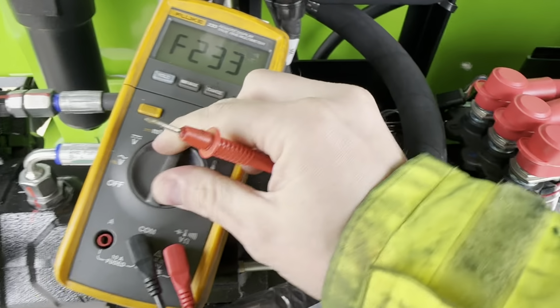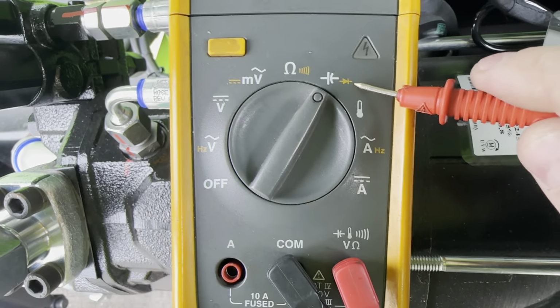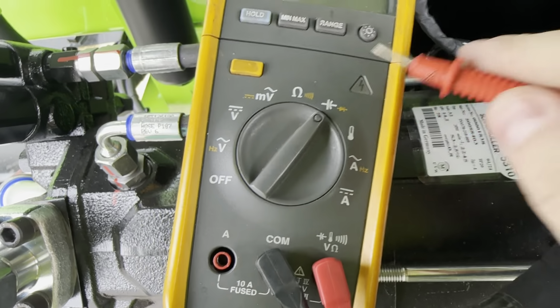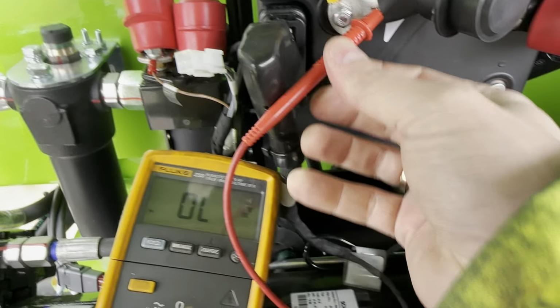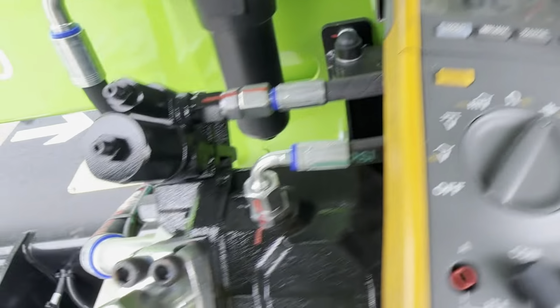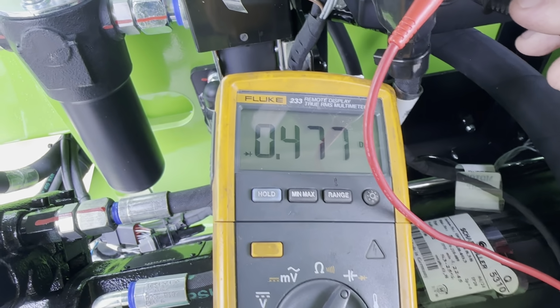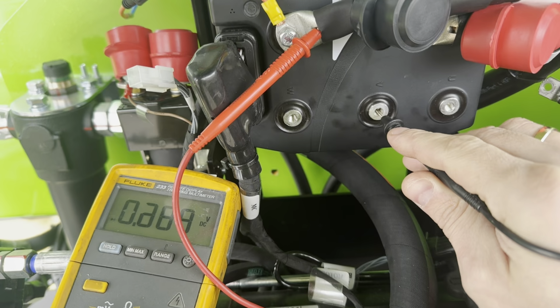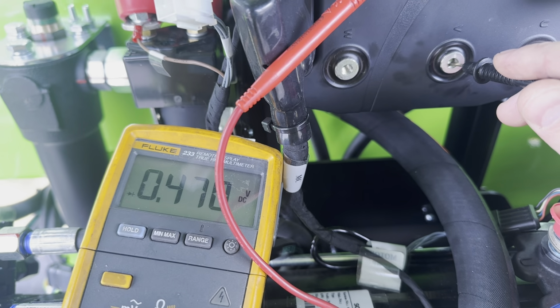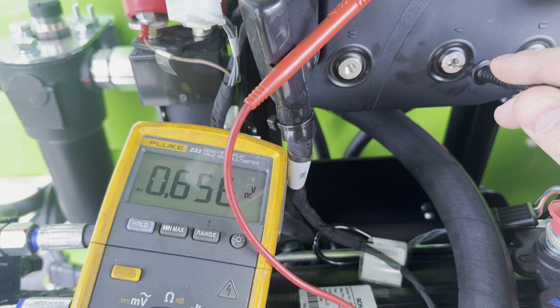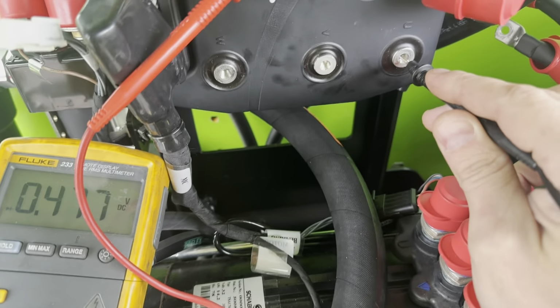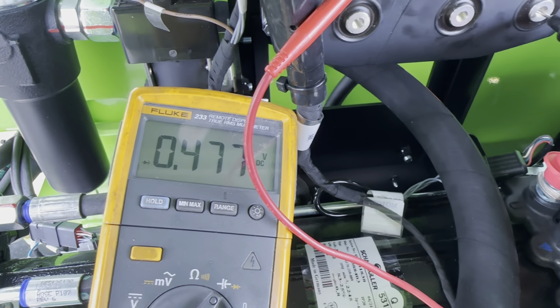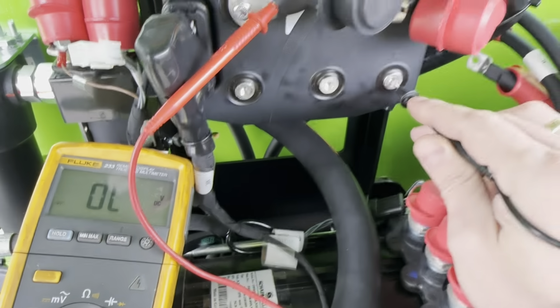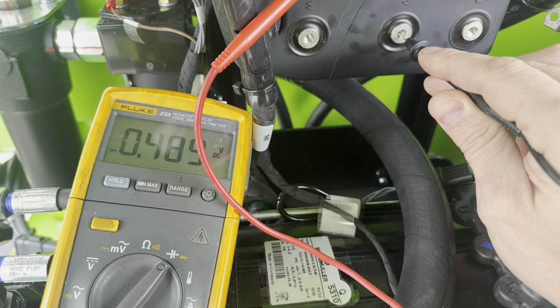So I'm going to set the multimeter to diode mode. On my multimeter, the diode mode is shared with the capacitance setting, and then with the yellow button I go into diode mode. The positive of the multimeter goes onto the negative, so that's B minus, and the negative we're going to put on the phase, and that should read a diode drop, yeah, so 0.4. So this one is good. You see, there is something wrong with this phase. It's climbing up. So that's phase V, and U is alright because we're getting the diode drop right away, yeah? Same. So W and V will be fine. It's something happening with this phase here.